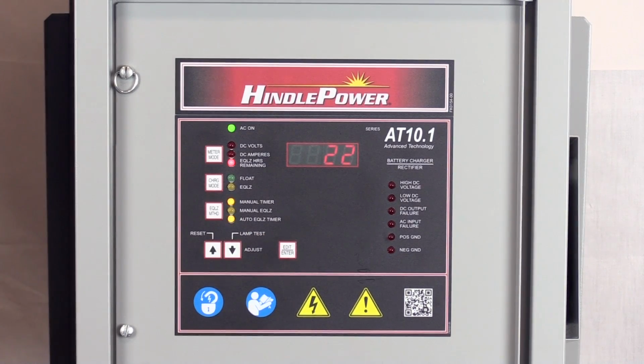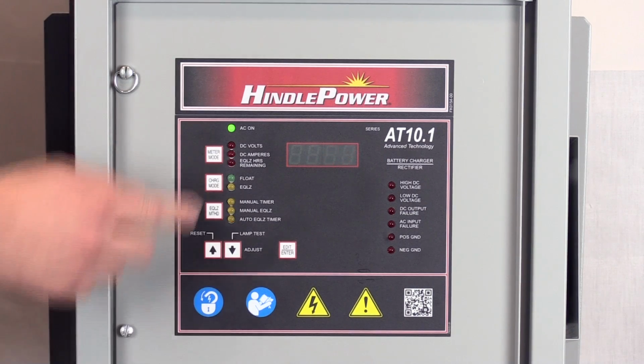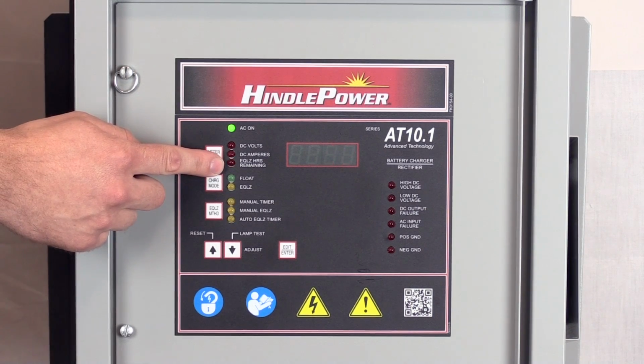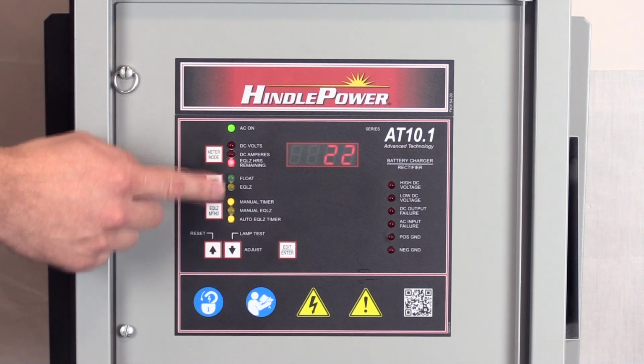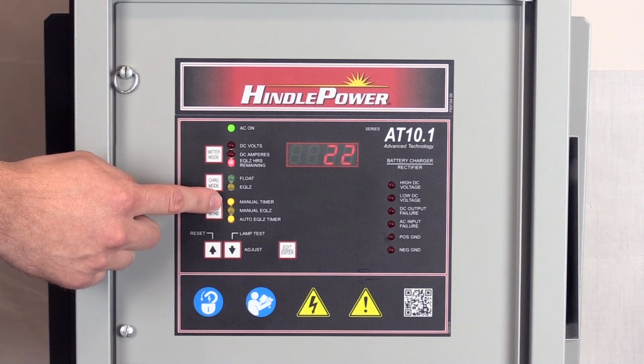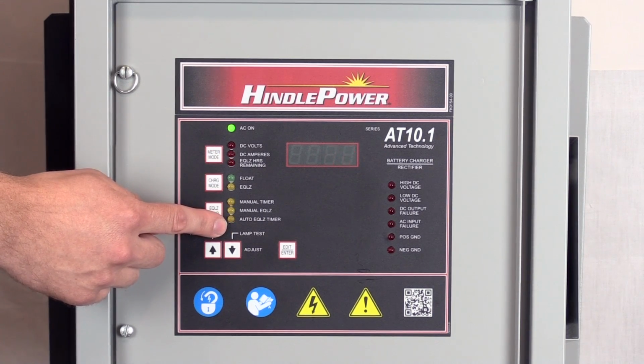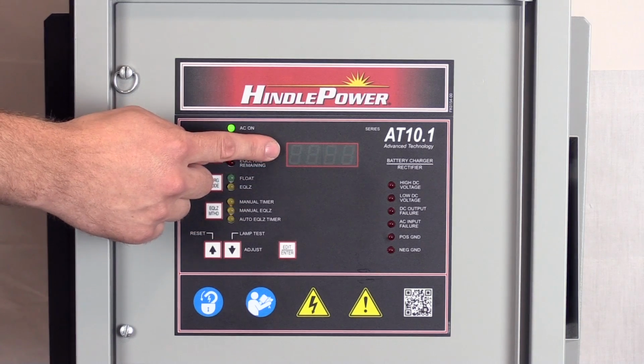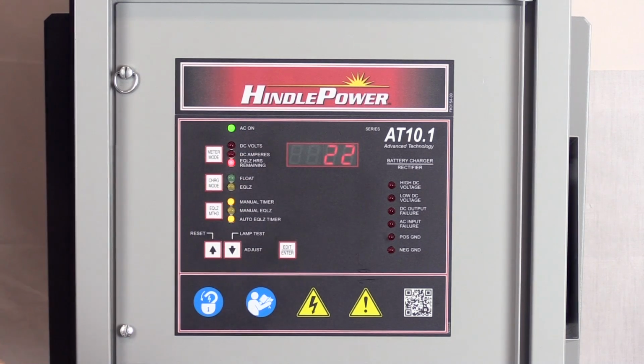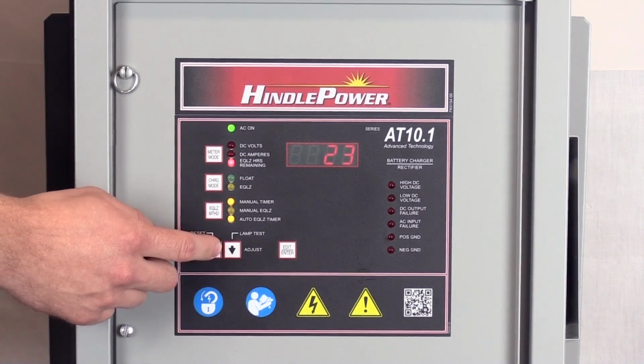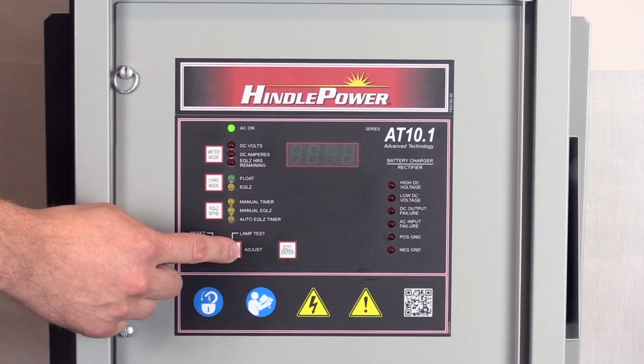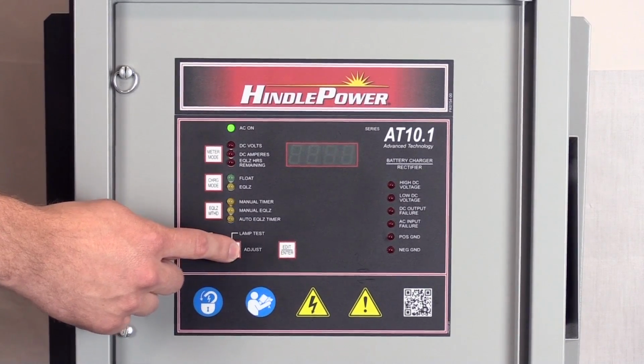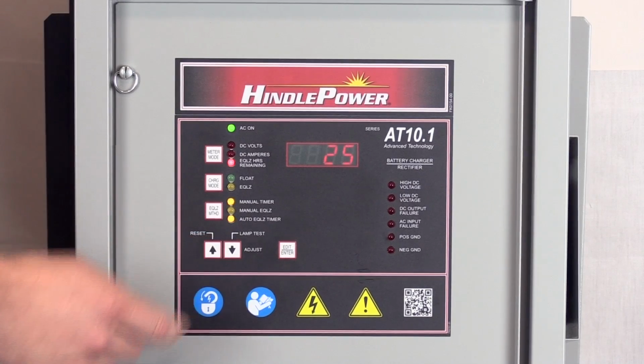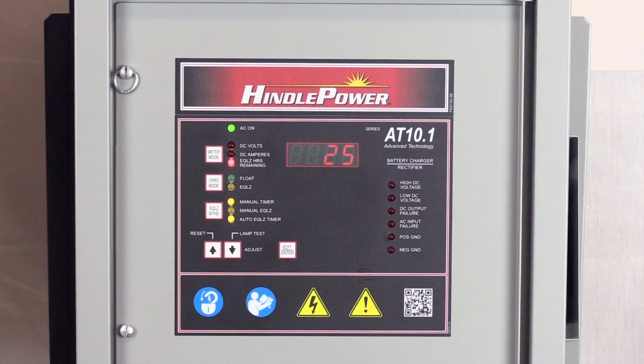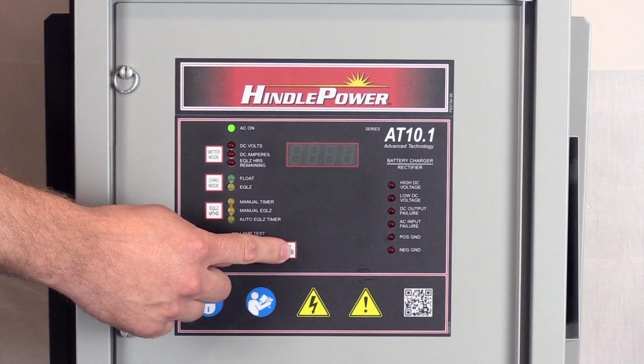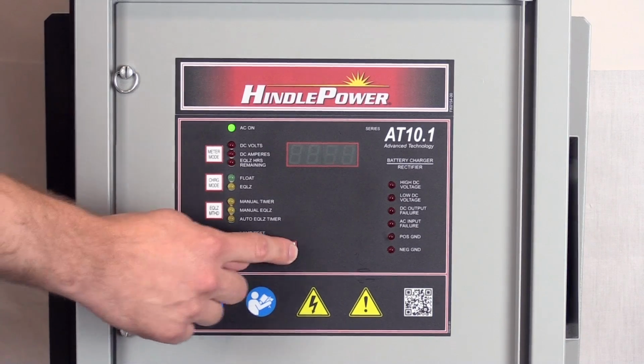The next parameter is the equalize timer hours. The red equalize hours remaining LED will flash. The yellow LEDs, manual timer and auto equalize timer, will flash, and the LED display will flash the equalize hours. Press the up and down arrow keys to adjust the set point. Press the Edit Enter key, and this will save your changes and go on to the next parameter.